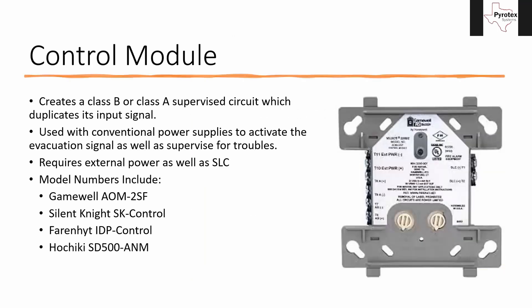A part we haven't talked about much is the control module. It looks just like the relays we've talked about, but the terminals are actually different. What it does is take some kind of external power or external speaker source and duplicate that circuit, putting it out as a Class B or Class A supervised circuit based on whatever that input is. It doesn't create any more power — it still uses the power from the original power supply or amplifier, but it adds supervision to the circuit.